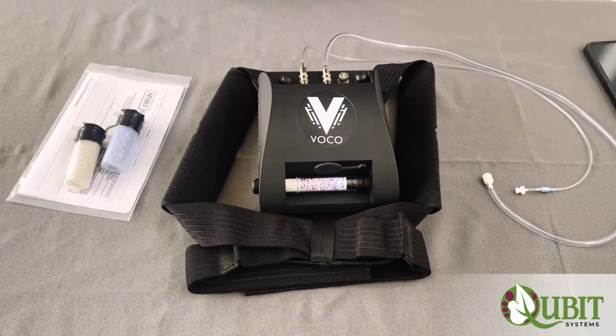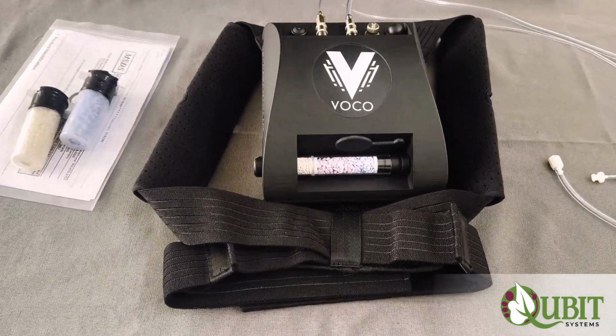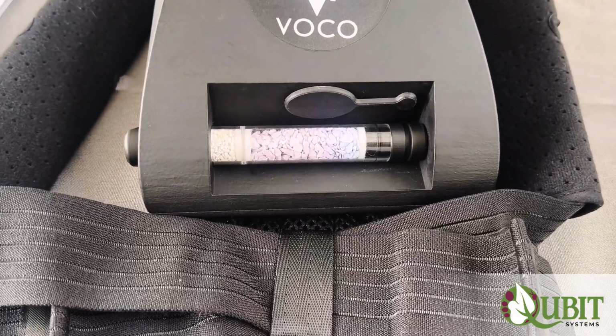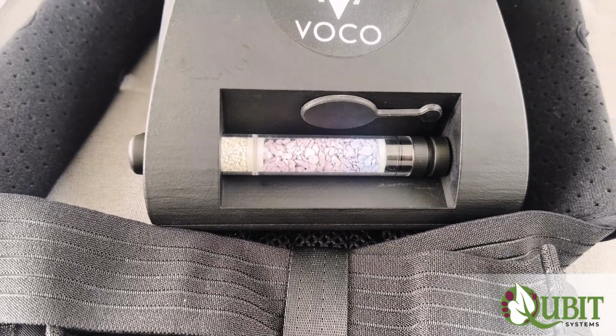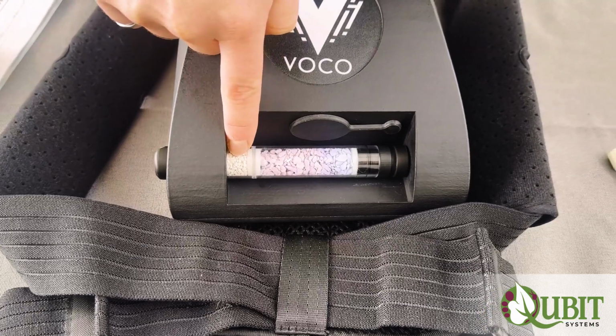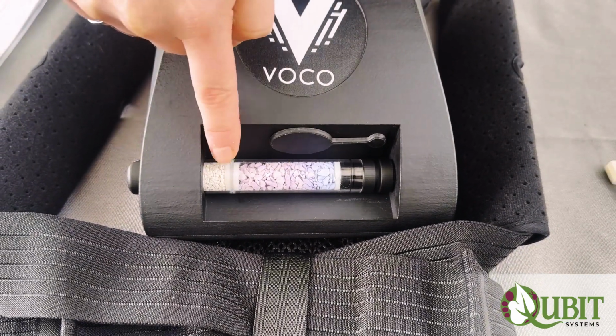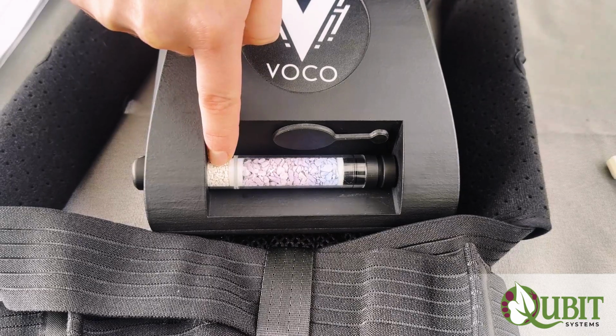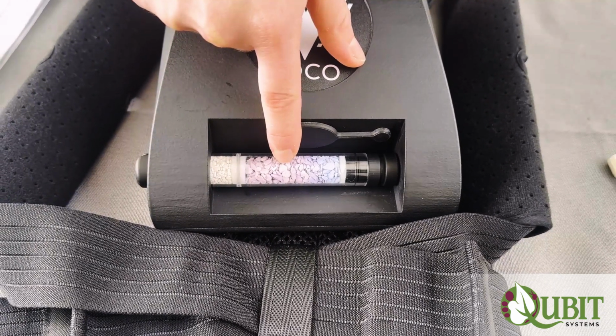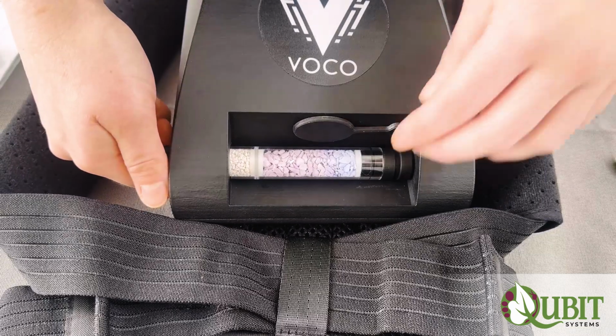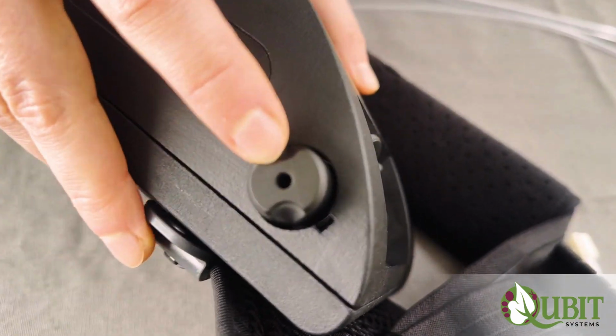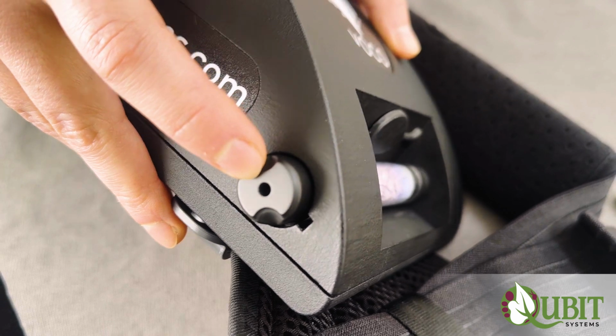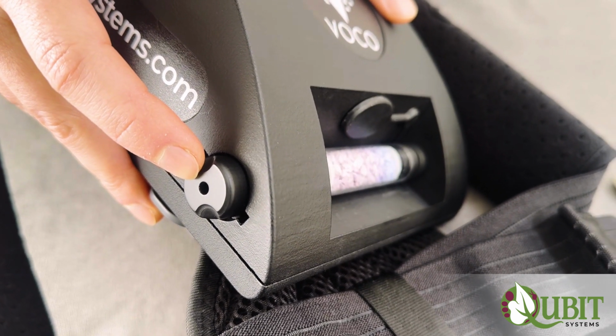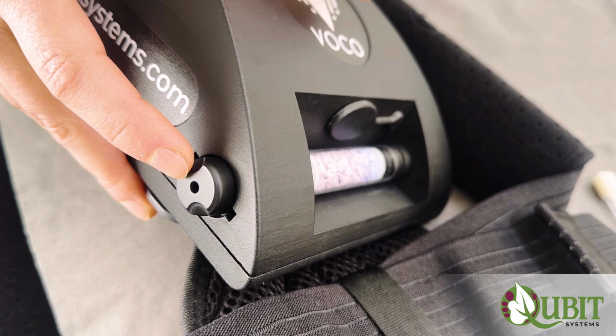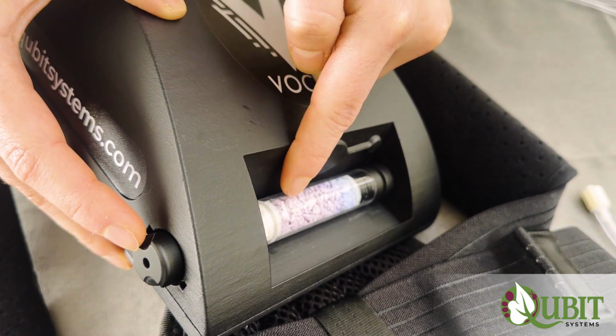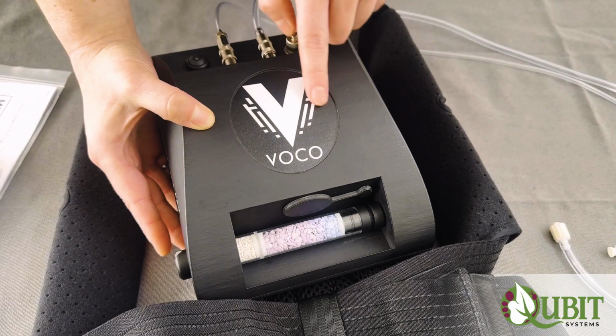In this video, we will be discussing the VOCO calibration column. The VOCO calibration column removes CO2 and moisture from a gas stream to calibrate the VOCO device. So the column contains soda lime here and Drierite right here. Soda lime removes CO2 from a gas stream, and Drierite removes moisture from a gas stream. So on the side here is a little gas port, and during a calibration, an internal valve on the VOCO will switch, and then gas will be pulled from this hole through the soda lime, through the Drierite, and into the VOCO sensors for calibration.